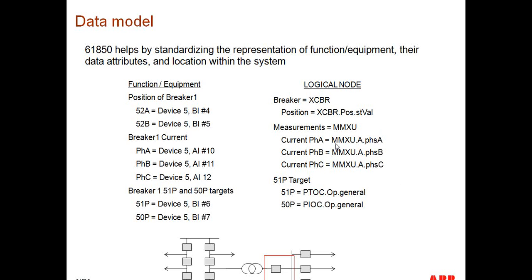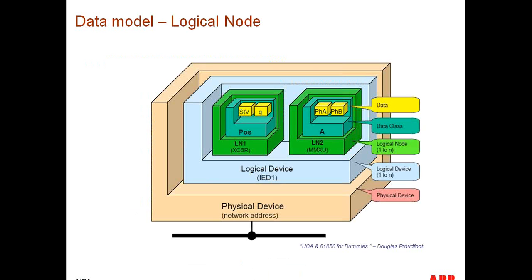No, you're going to see a digital value that has this particular name structure. So in the case of, let's say, a breaker fail function, you're not going to get a 1 or a 0. You're going to get this complete structure. So then at least you can understand that the signal that my device is receiving comes from a protection function. So from a documentation perspective and building protection schemes, this naming convention really facilitates that.